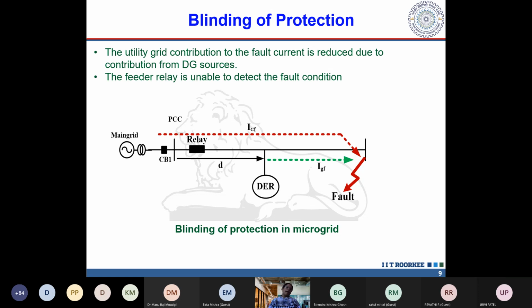So why does it happen? For that I have taken this picture. This is the main grid, this is the PCC, and here is the relay location, and this is one feeder which originates from this PCC bus. This is the point where the renewable source is integrated into the feeder. And there is a fault in front of this DER.